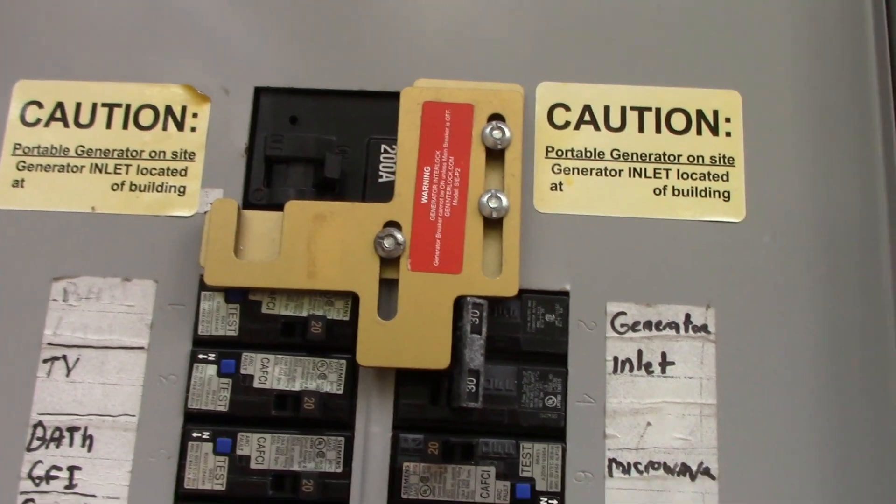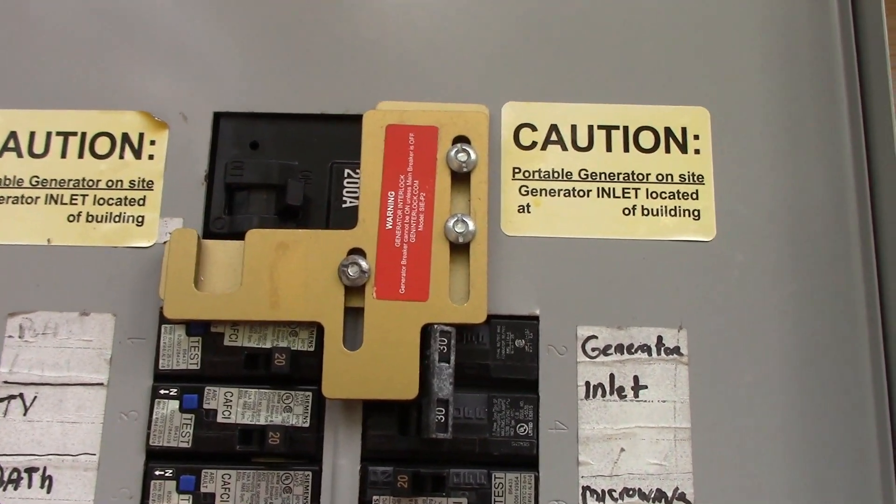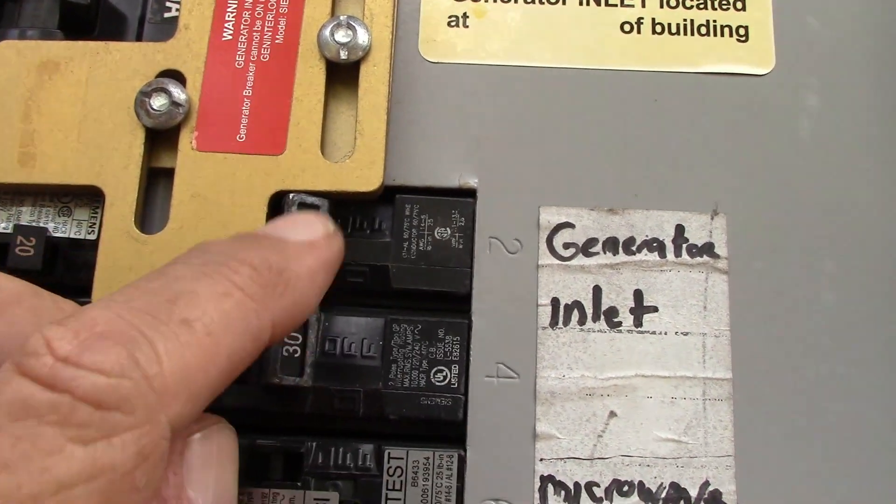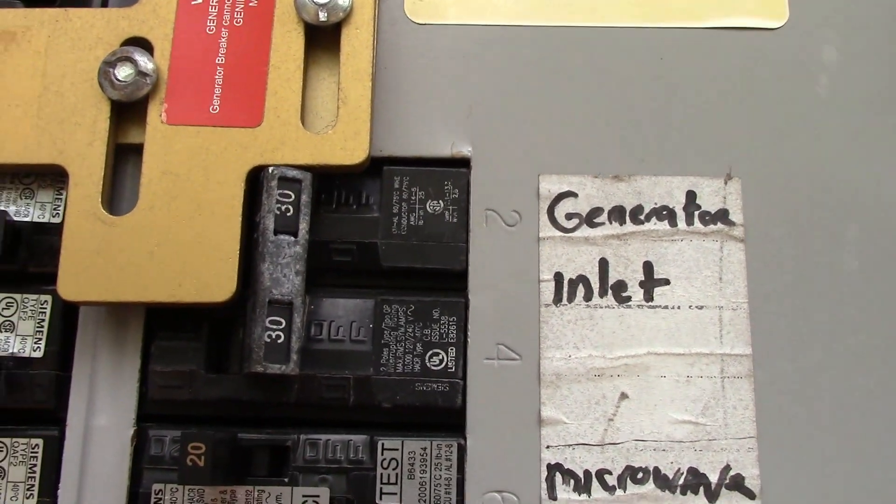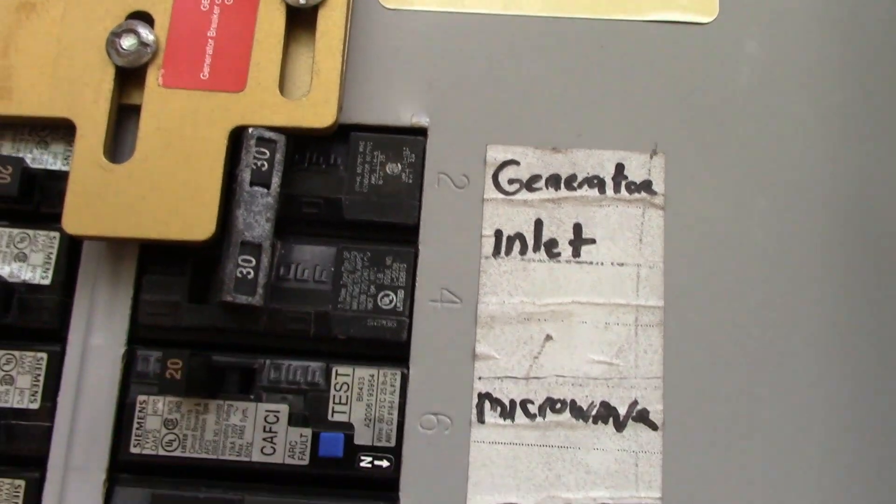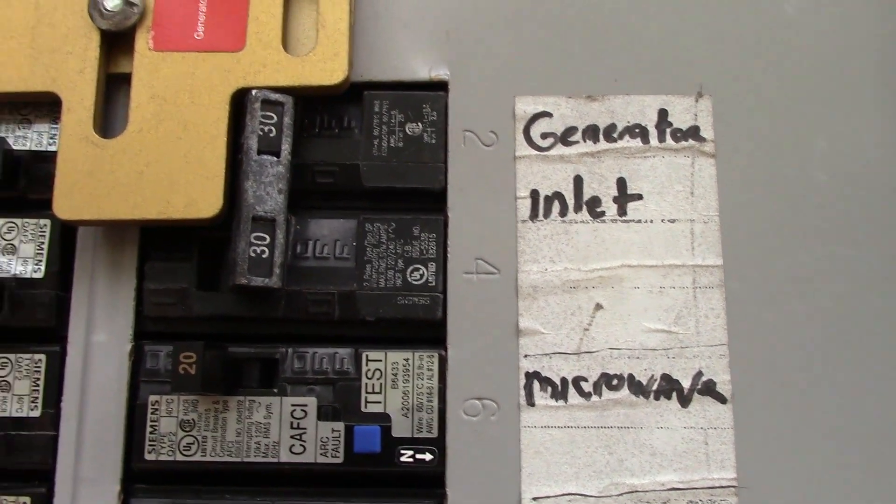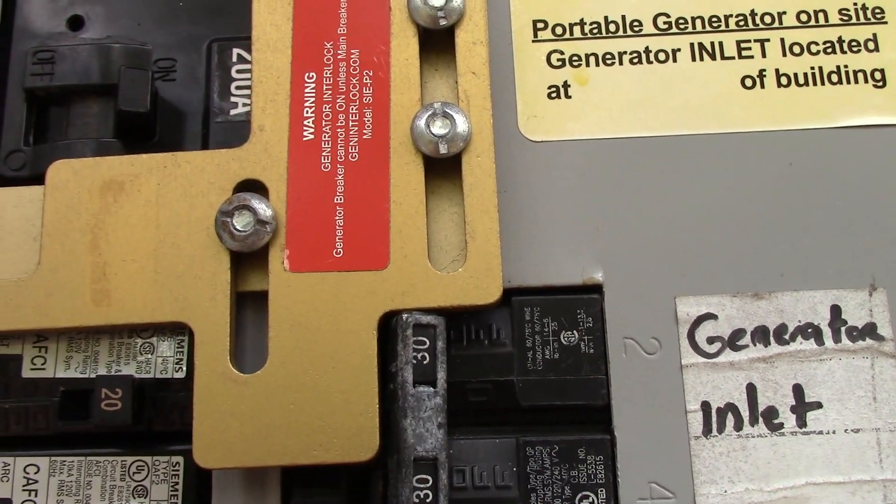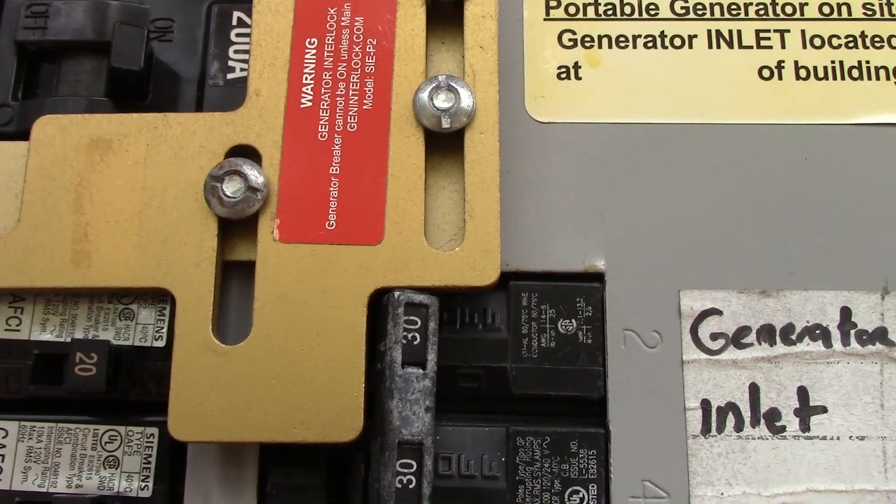That goes up to the interlock kit. As you see, this is the generator breaker here - it's also connected to the solar inverter. Basically, if I were to flip this breaker on, I would have power coming into this panel here. But that can't happen when you have the main breaker on. At the same time, if the power is off from a storm, then you'd be back feeding the line. So you have an interlock kit.